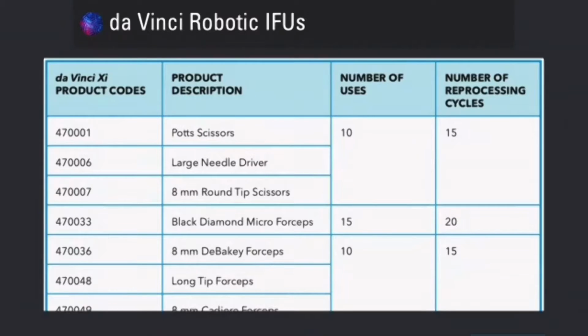But in the case of the black diamond micro forceps, its number of uses is 15, but you can reprocess it 20 times. So there's a difference of 5 times, let's say, that it could be in the OR open and not actually docked with the robot or used. But I also want to point out that the numbers of uses differ: 10, 15, 10 for the 8 millimeter DeBakey forceps. All your robotic instruments don't always have the same number of uses available to them. So I do recommend you look into the indices that are available wherever you can find your IFUs, which I'll mention a little bit more about in a moment.